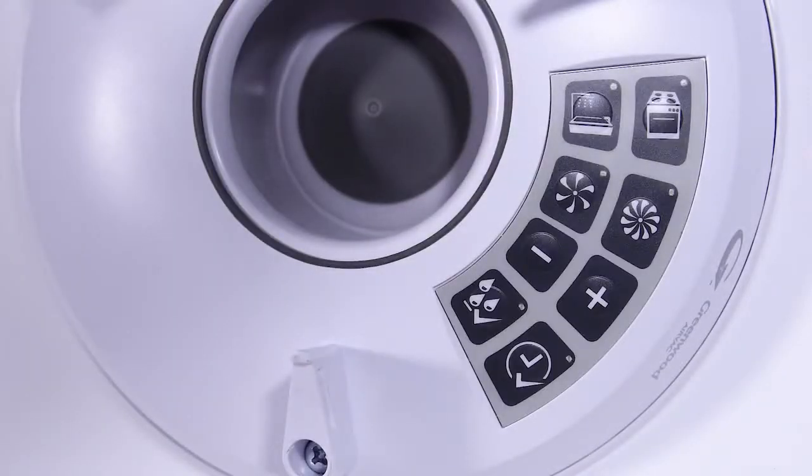HumidiSmart monitors the humidity of the extracted air at all times, switching to boost mode if there is a rapid rise in humidity, typically from a shower or bath. When humidity falls below a calculated threshold close to background levels, the fan should return to trickle mode.